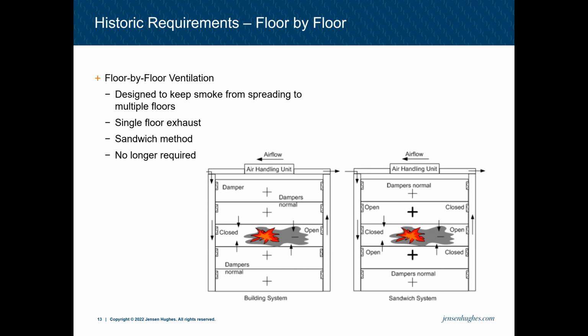These have started to not be required anymore as they are cumbersome. In high-rise buildings, there are a lot of moving parts. Semi-annual tests have shown that buildings haven't been maintained super well with these types of systems. More and more testing has been done to keep these systems as they were designed to, but a lot of dampers break and it requires a lot of replacement. But if we're in a building that's being renovated with this type of system, we have to maintain it the way it was designed to, because these can cause issues if it doesn't operate correctly. For example, a supply damper not opening at the correct time could fuel the fire and make conditions worse. So it's important to keep these functioning to what they were designed to.